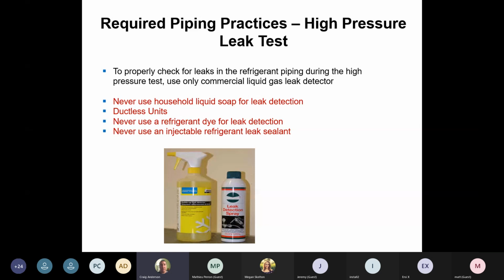Because there's EE valves, which is the valve that modulates the freon going to the indoor unit, that little valve can move 480 positions. There's strainers on it. We can't have anything that will slow that EE valve down or gum it up or anything like that. So anything that has variable speed, variable speed air conditioners, or you get into your mini splits, do not use your dye or your refrigerant leak sealant. Standard air conditioners we're okay with.